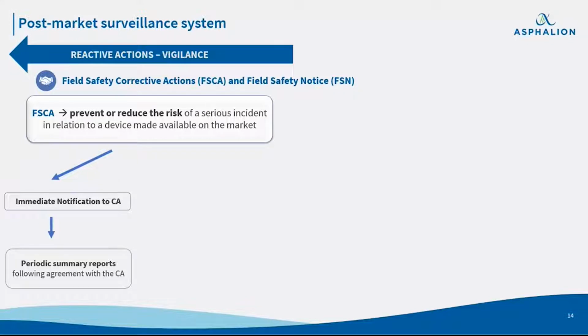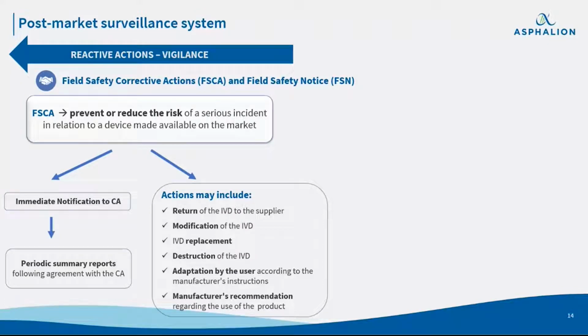Which action may include an FSCA? It can include return of our IVD, modification of the IVD, IVD replacement, destruction, adaptation by the user according to the manufacturer's instructions, manufacturer's recommendation regarding the use of the product. It's very important for you to know that the field safety corrective action must apply in all countries where the affected in vitro medical device is on the market or is still in use. Besides, an FSCA goes hand in hand with a field safety notice.